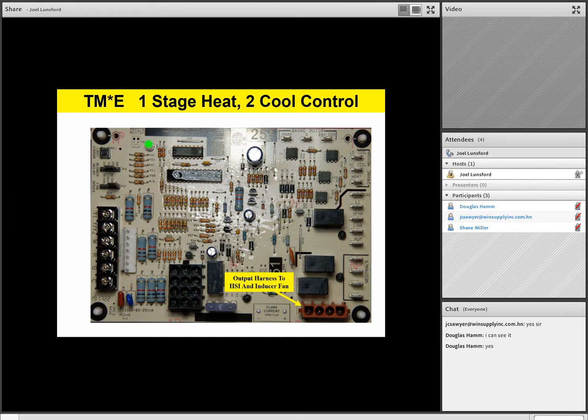Naturally, when this board is installed in the furnace, all this stuff is going to be harnessed in. Your neutrals will be plugged in, your transformer will be hooked up, and all these harnesses will be plugged in, so the technician doesn't have to do that during install. It's just that we've removed all those harnesses in the photos for training purposes. So don't worry about what you have to hook up if a technician has this board. If he has to replace the board, naturally he'll have to take all the harnesses off and replace all the terminals and so on. Anyway, this is the output harness to the hot surface igniter and the inducer fan motor.